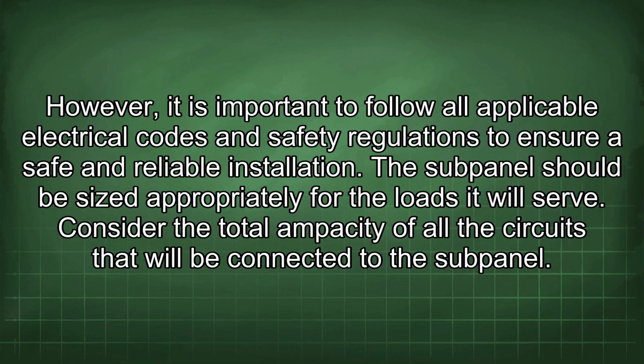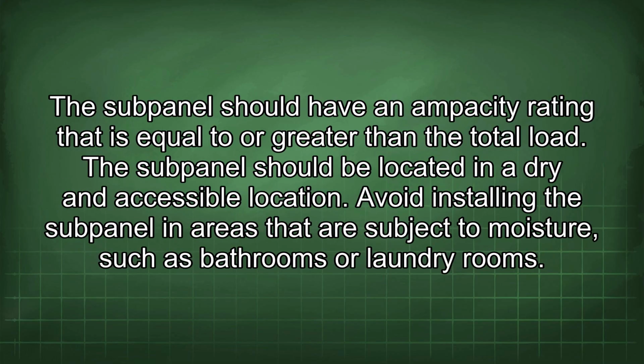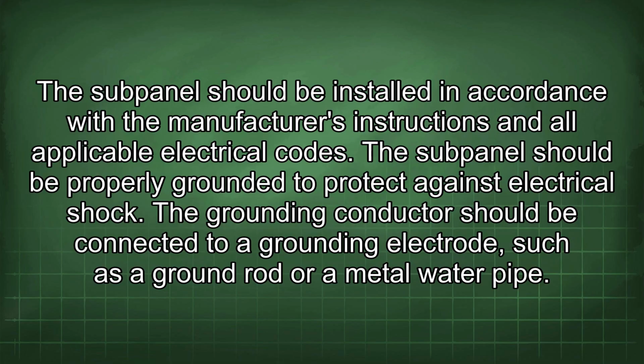The subpanel should be sized appropriately for the loads it will serve. Consider the total ampacity of all the circuits that will be connected to the subpanel. The subpanel should have an ampacity rating that is equal to or greater than the total load. The subpanel should be located in a dry and accessible location. Avoid installing the subpanel in areas that are subject to moisture, such as bathrooms or laundry rooms. The subpanel should be installed in accordance with the manufacturer's instructions and all applicable electrical codes.